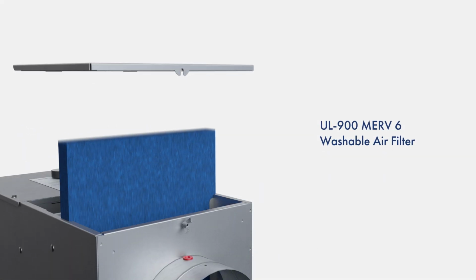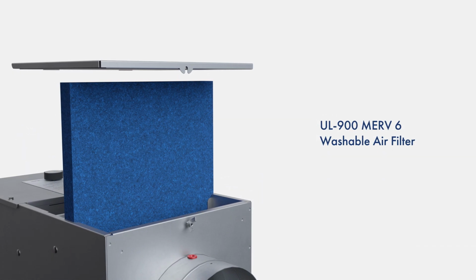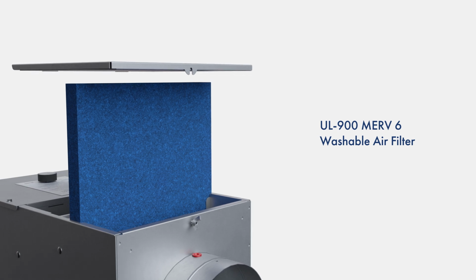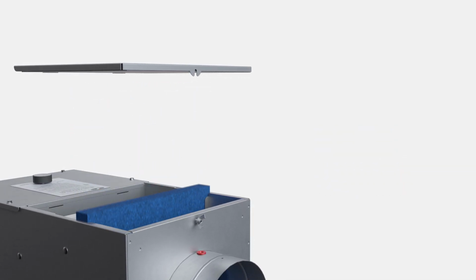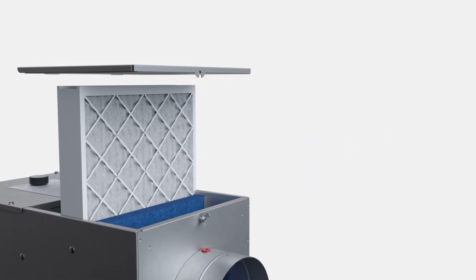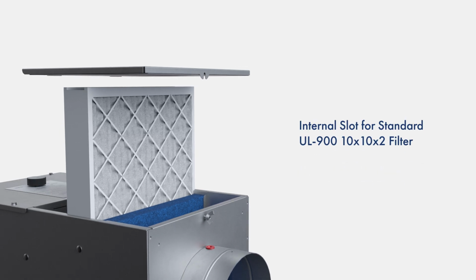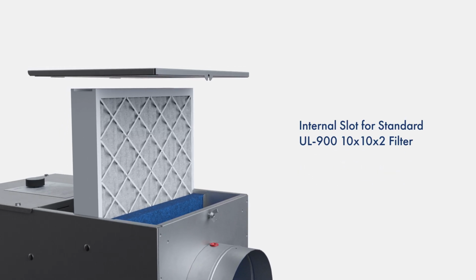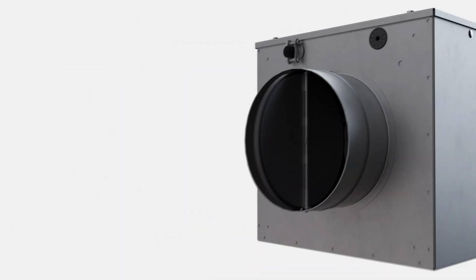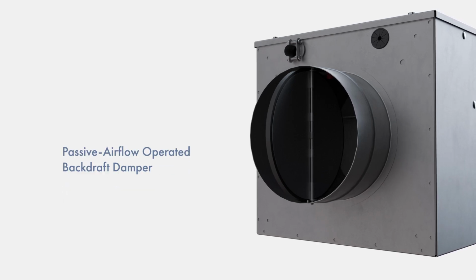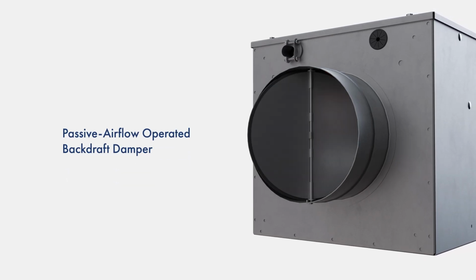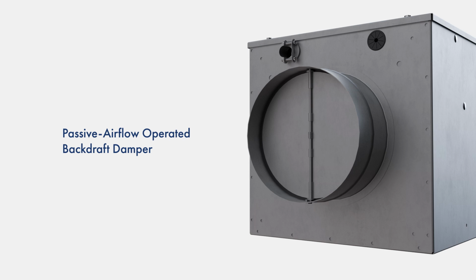The FAPV is provided with a washable UL 900 rated MERV 6 intake air filter. The designed gasketed second filter slot accepts a standard UL 900 rated 10 by 10 by 2 inch filter. Finally, the FAPV is equipped with a backdraft damper that minimizes unwanted ventilation during the off cycle.